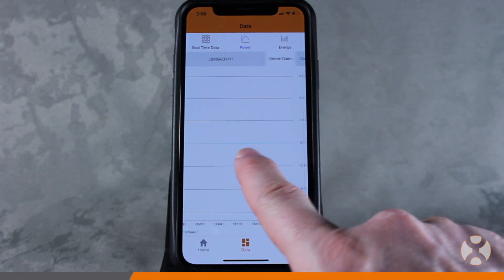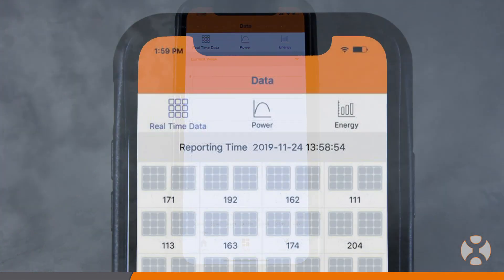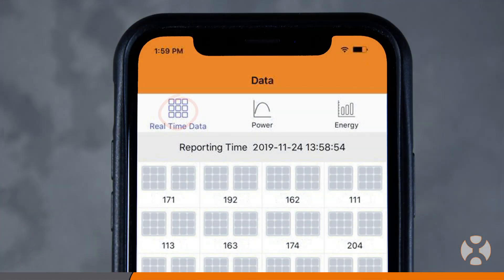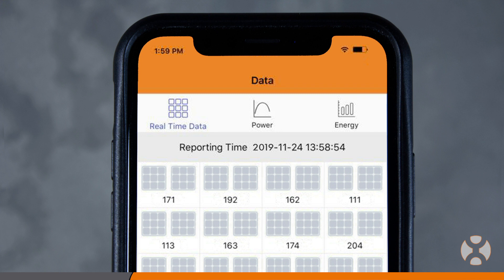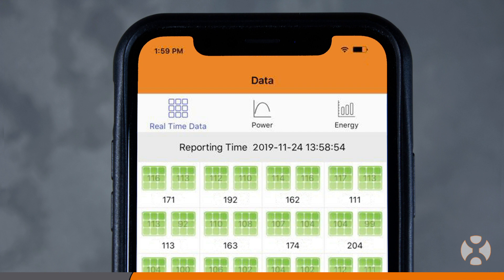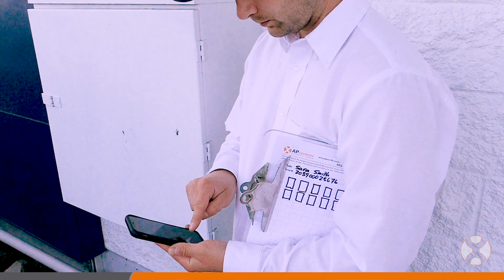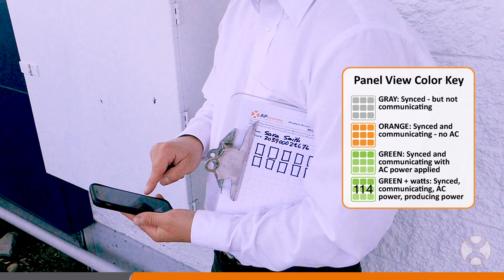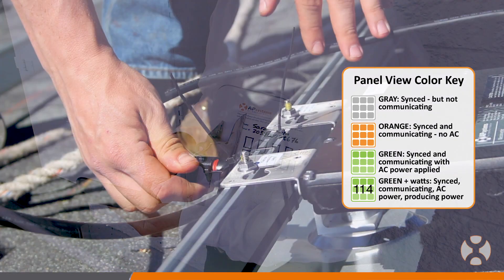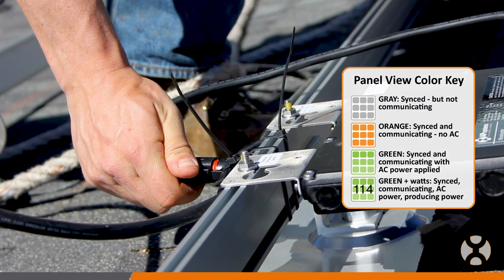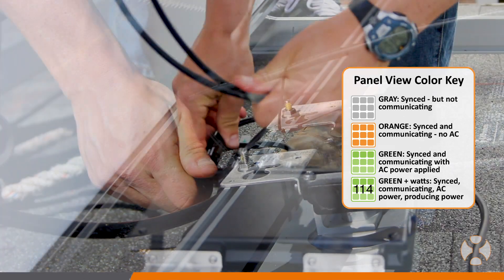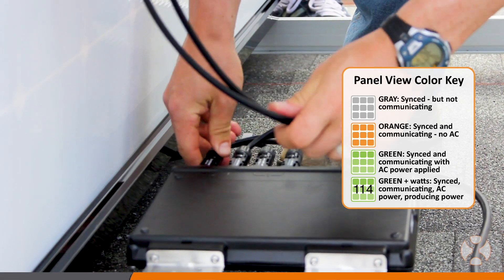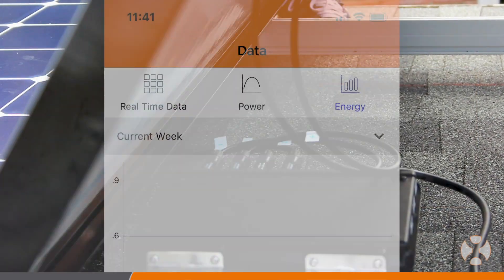To verify connection to the microinverters, click on the real-time data option, and you'll see each PV module as well as the last few digits of each microinverter serving those modules. Once all the PV modules and microinverters are connected, the module icon will turn green when AC power is applied and will display a wattage when they are producing power. If any display is gray, the installer should check the UID serial numbers they entered and synced for accuracy before checking cabling connections between the inverter and the AC bus trunk cable and between the inverter and the PV modules.